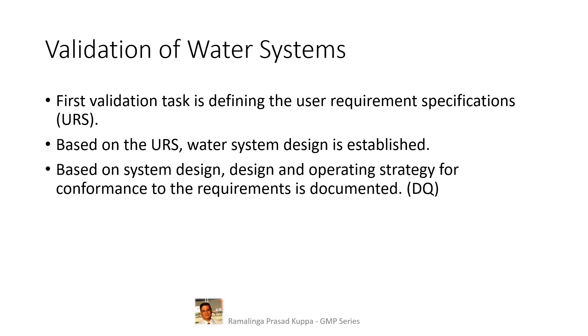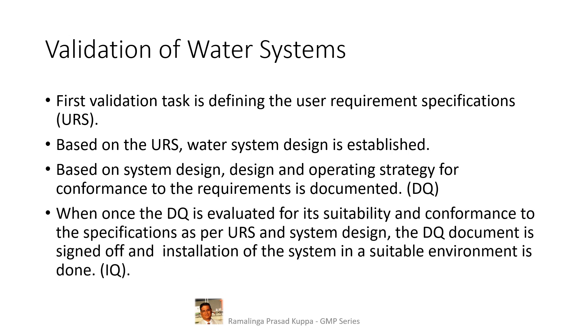Based on system design, the operating strategy for conformance to requirements is documented as DQ. At this milestone, design and operating strategies are documented in detail and signed off as approval of design qualification. When the DQ is evaluated for its suitability and conformance to the specifications as per URS and system design, the DQ document is signed off and installation of the system in a suitable environment is done — that is IQ.